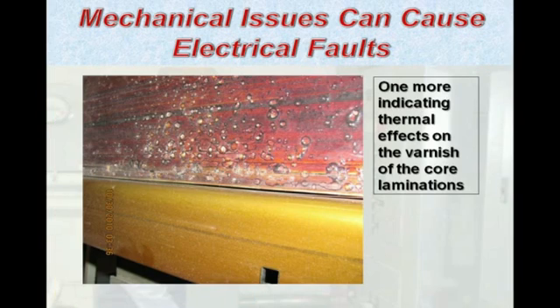Another view of the core clearly shows the heating damage based on the thermal effects of the energy being generated, where it was literally bubbling up the varnish that was on the core. Because they dip these things in varnish at manufacture, seal everything up. That was starting to peel off due to the heating effects.